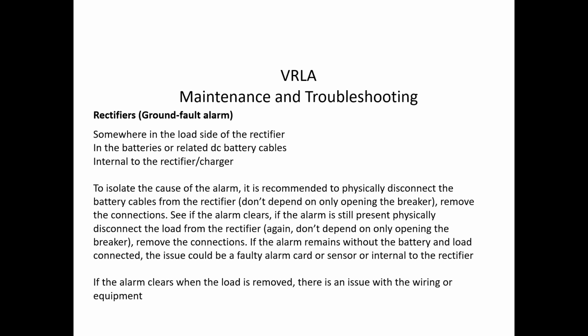There are 3 places where those alarms can be caused: load, somewhere in the battery or the cables, or internal to the rectifier itself. It's not uncommon or unheard of to actually have the alarm come from either a faulty card or someplace within the rectifier itself. Again, to troubleshoot or isolate the alarm is a little difficult when in service. We recommend identifying which one of those 3 places the alarm is coming from.